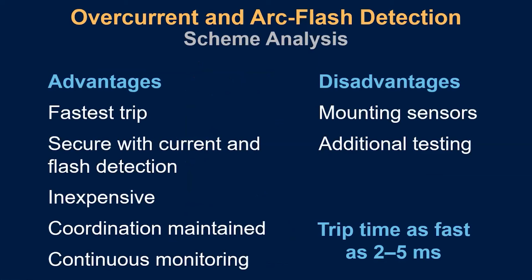down to beating the filters in the relay even, and calling for a trip in as little as 2 to 5 milliseconds, coupling that with our high-speed contacts on the relays, which have an operating time of about 50 microseconds. We are now looking at an arc flash incident energy that's dependent pretty much just on breaker operating time. And so we've gotten about as fast as one possibly can get with the existing breaker technology we have today.